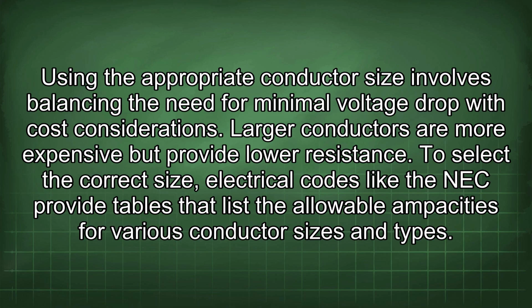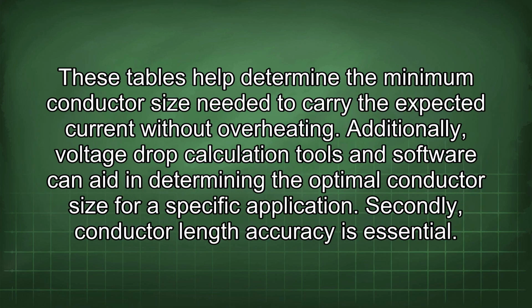To select the correct size, electrical codes like the NEC provide tables that list the allowable ampacities for various conductor sizes and types. These tables help determine the minimum conductor size needed to carry the expected current without overheating. Additionally, voltage drop calculation tools and software can aid in determining the optimal conductor size for a specific application.